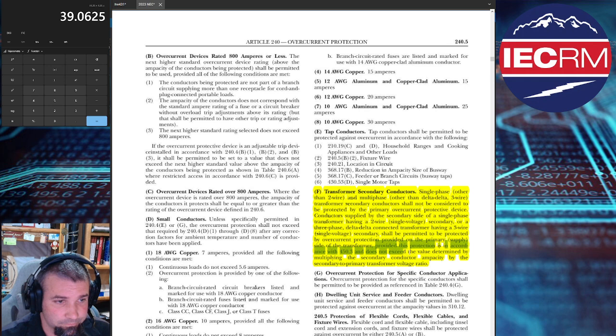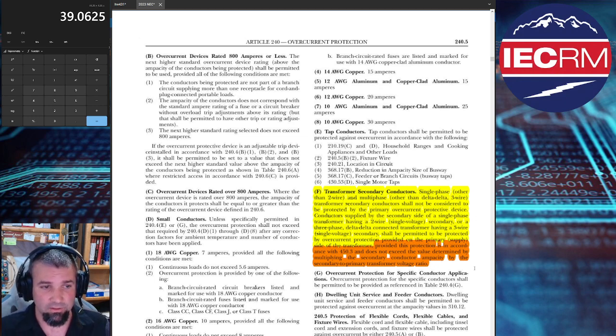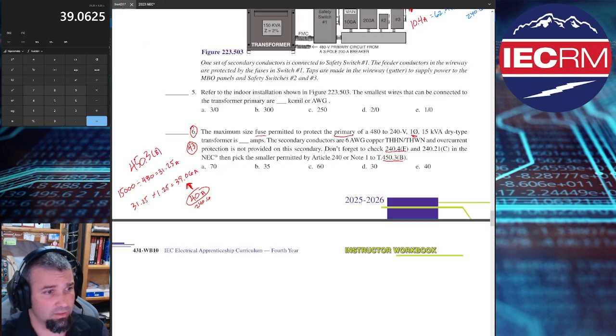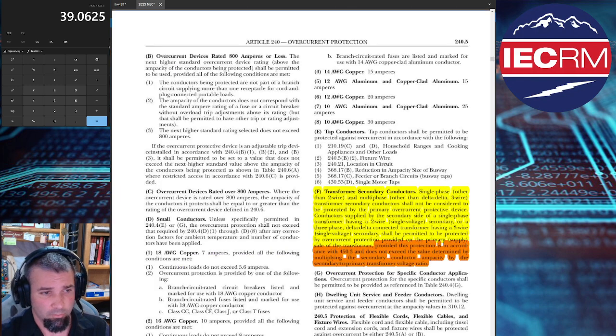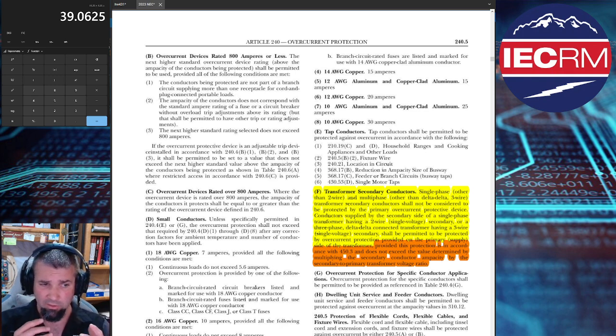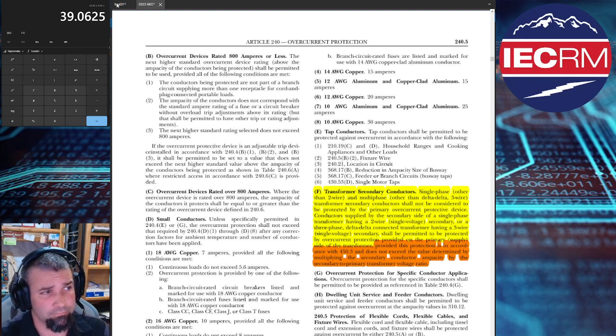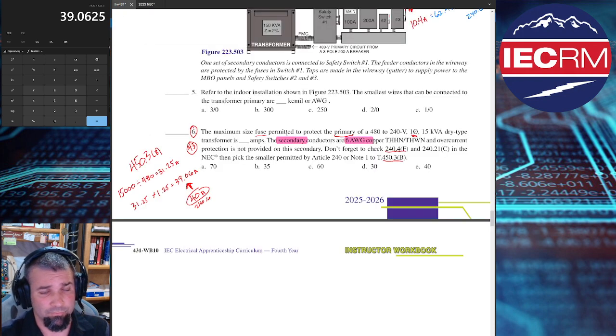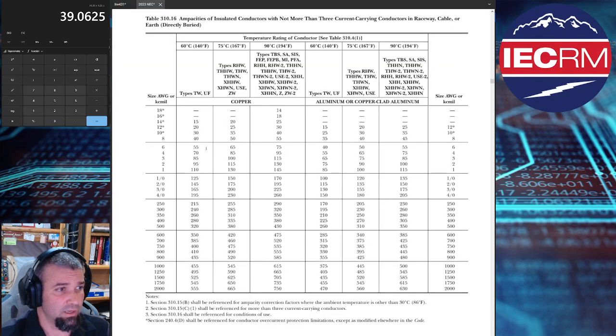It says provided. This protection is in accordance with 450.3 and does not exceed the value determined by multiplying the secondary conductor ampacity. So that's going to be the ampacity of this number 6. Okay, it says the secondary conductors, right? By multiplying the secondary conductor ampacity by the secondary to primary transformer voltage ratio. Made that a little confusing. Okay. Let's figure it out. We got this. Okay, so I am going to go figure out what a number 6 is worth. Okay, let's head over to that holy grail article 310.16. I'm going to find that number 6.